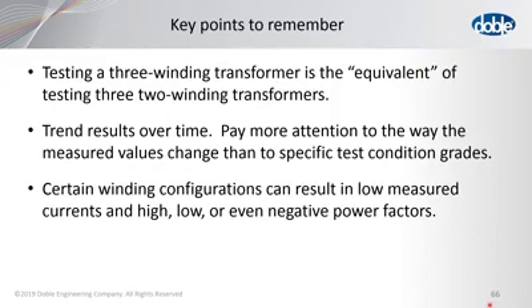You want to trend results over time. So in other words, pay attention to changes from one testing year to another. Also, certain winding configurations can result in low measured currents and high, low, or even negative power factors, but don't indicate an issue.